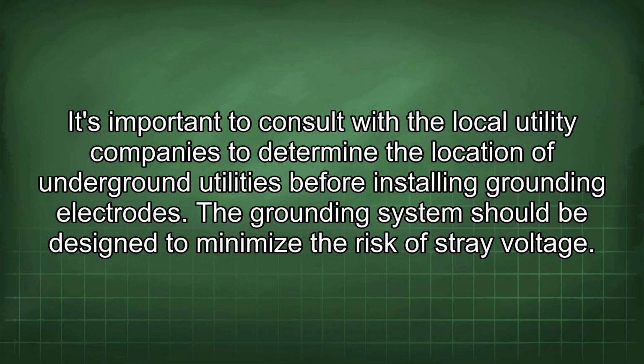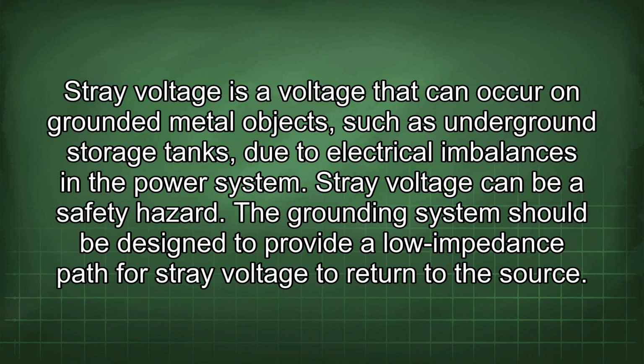The grounding system should be designed to minimize the risk of stray voltage. Stray voltage is a voltage that can occur on grounded metal objects such as underground storage tanks due to electrical imbalances in the power system. Stray voltage can be a safety hazard. The grounding system should be designed to provide a low impedance path for stray voltage to return to the source.